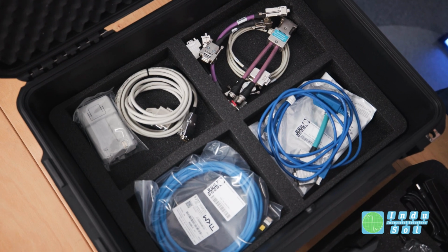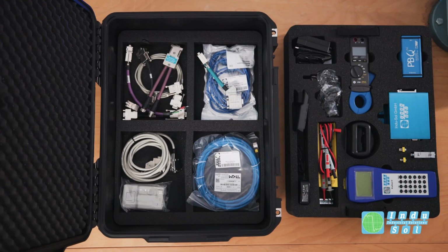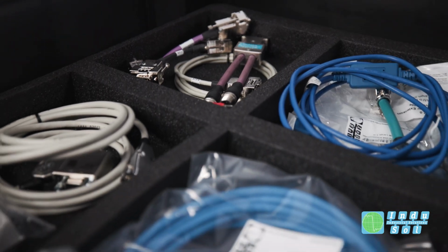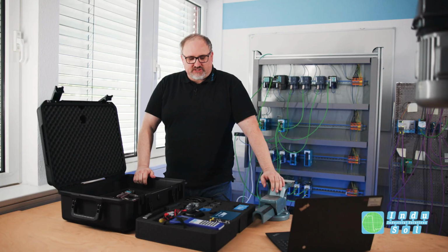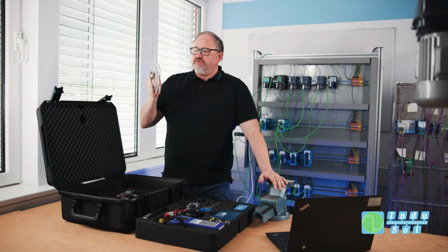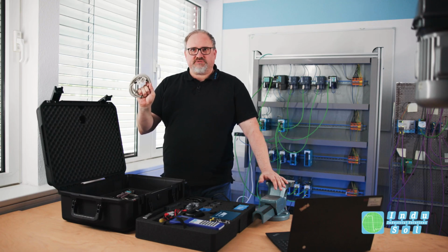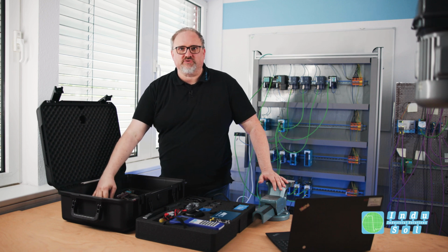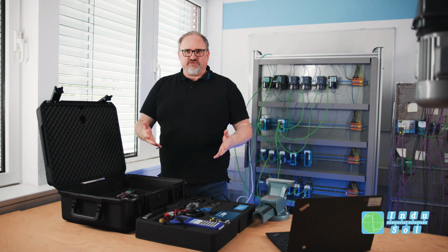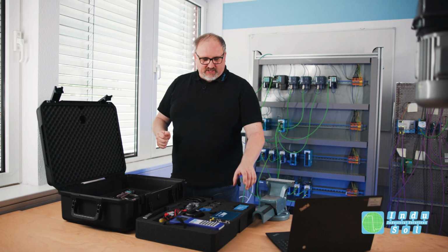Of course, we also need adapters for the tools in order to be able to use them, and these are located on the second level of the case. What kinds of adapters are there? I had already mentioned that the inspector could be connected to the control system with an active programming cable. It is really important to use such a cable and not to build one yourself, because that could cause feedback in your bus systems, and that would then cause an additional error or distort your measurement.